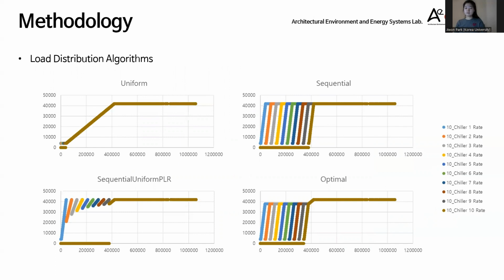First, the uniform algorithm evenly distributes the load among all chillers once the minimum PLR is reached. Second, the sequential algorithm utilizes the full capacity of each chiller and turns on the next chiller. Third, the sequential uniform PLR algorithm distributes the load evenly among the turned-on chillers while utilizing the full capacity of each chiller. Fourth, the optimal algorithm turns on the next chiller once the optimal PLR of 90% for each chiller is reached. In this research, we validate the effects of dividing the cooling load among multiple chillers using these four algorithms.